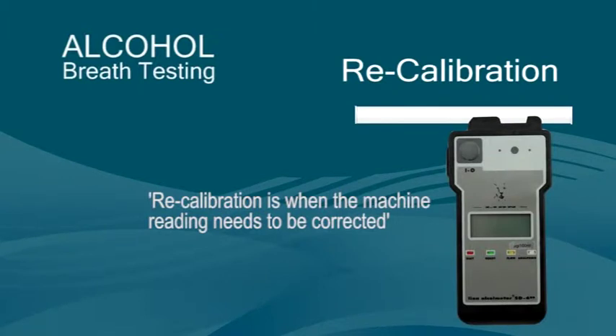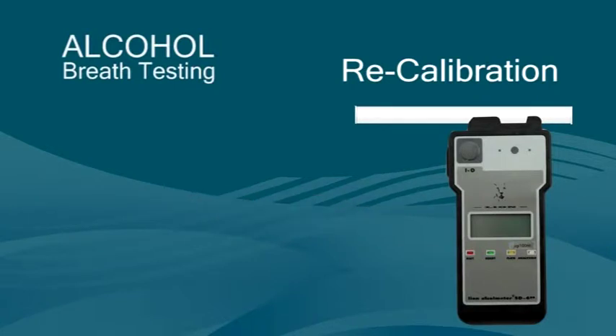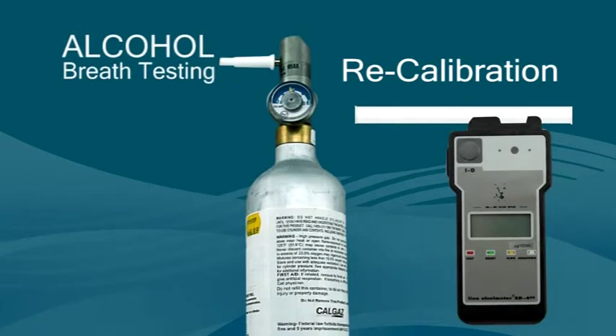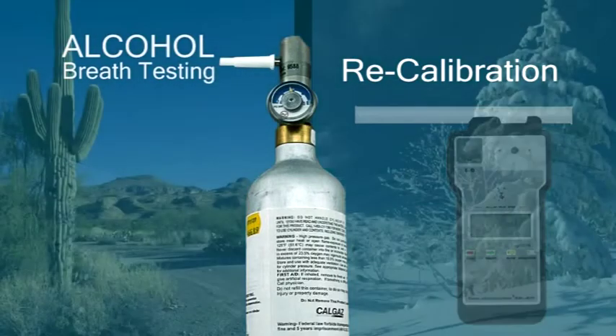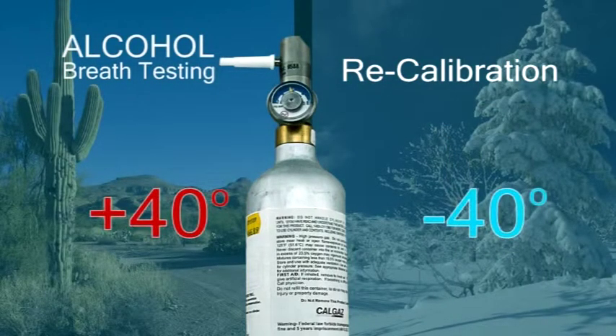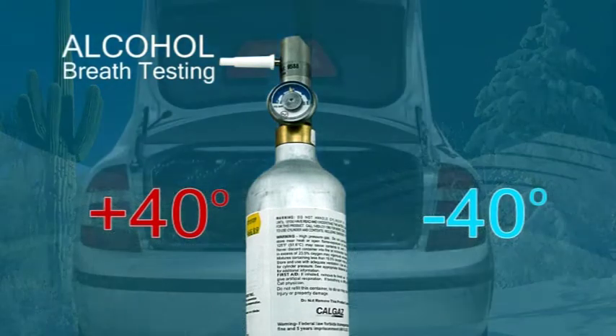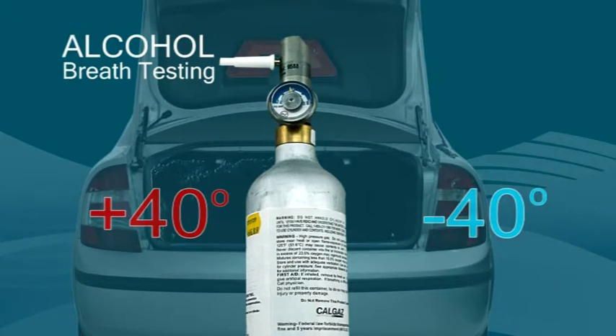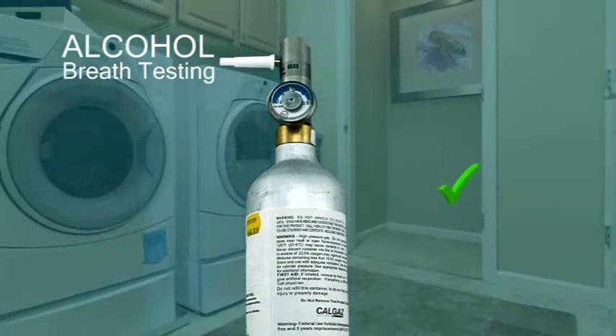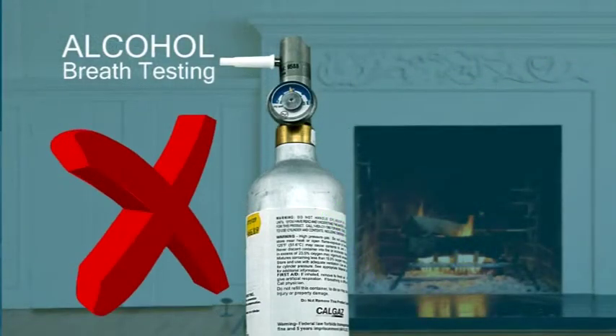With some machines, this must be done by the manufacturer, but with others, you can do this. Where you do this, both the calibration check and recalibration are done using a calibration gas containing a known level of alcohol. The procedures are straightforward. However, the gas in your cylinder is temperature sensitive, so try to keep the cylinder at an even temperature and do not use it straight from the boot of your car in very cold or very hot weather. When not travelling, keep the gas indoors, but away from direct heat.